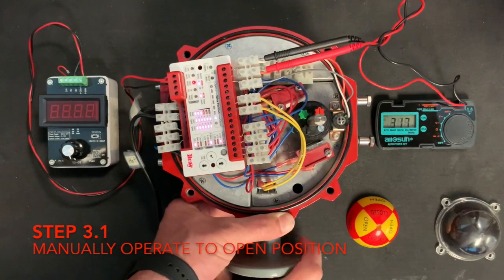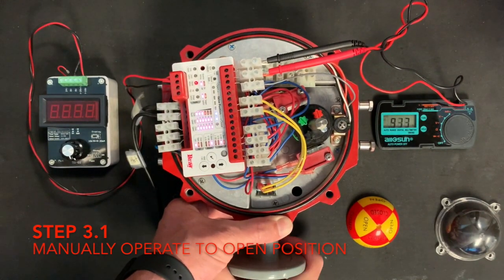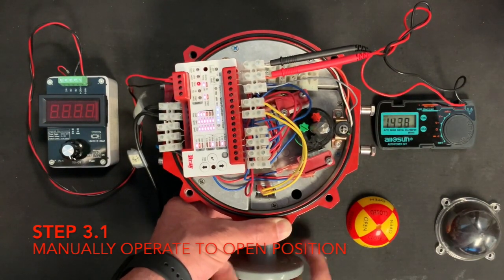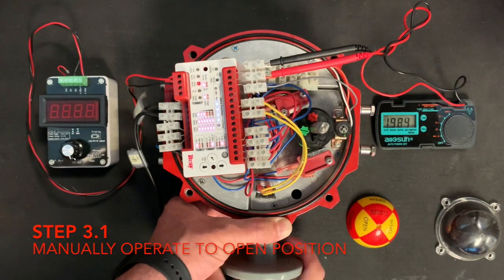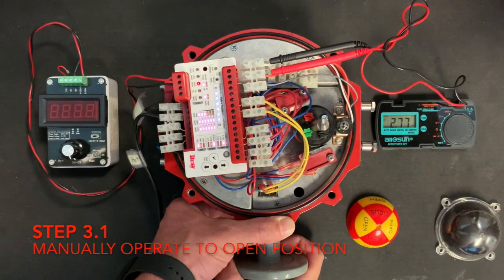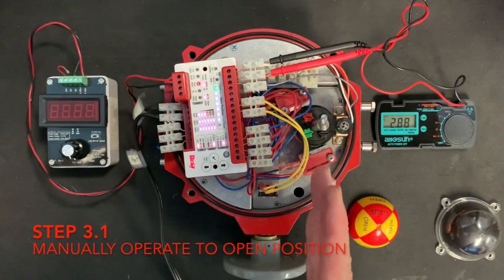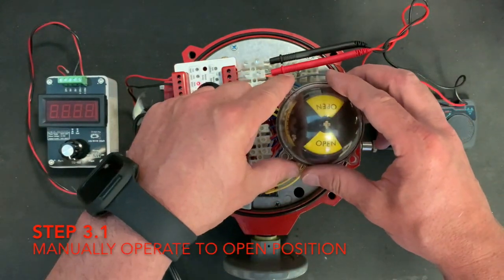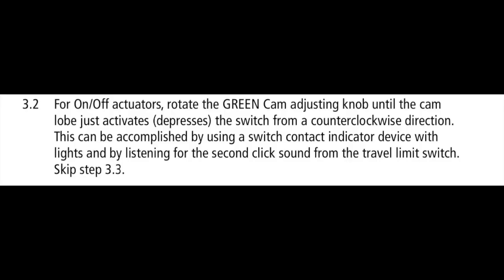Manually operate the actuator hand wheel counterclockwise until the valve reaches the desired open position. For on-off actuators, rotate the green cam adjustment knob until the cam lobe just activates, depresses, the switch from a counterclockwise direction. This can be accomplished by using a switch contact indicator device with lights and by listening for the second click sound from the travel limit switch.